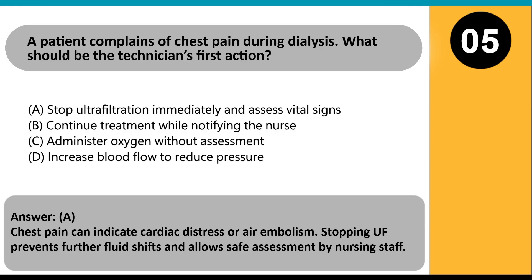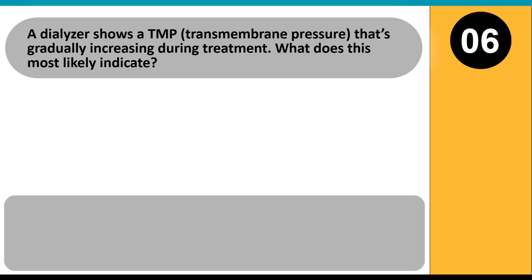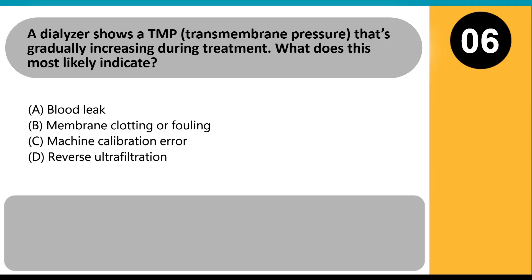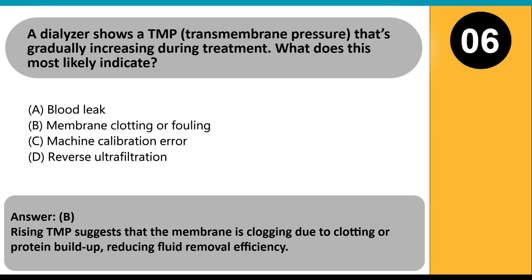Stopping UF prevents further fluid shifts and allows safe assessment by nursing staff. A dialyzer shows a TMP (transmembrane pressure) that's gradually increasing during treatment. What does this most likely indicate? A. Blood leak. B. Membrane clotting or fouling. C. Machine calibration error. D. Reverse ultrafiltration. Answer B. Rising TMP suggests that the membrane is clogging due to clotting or protein buildup, reducing fluid removal efficiency.